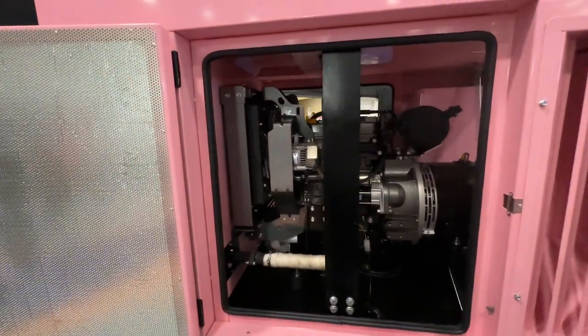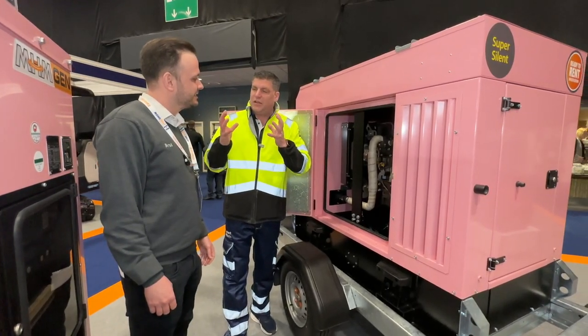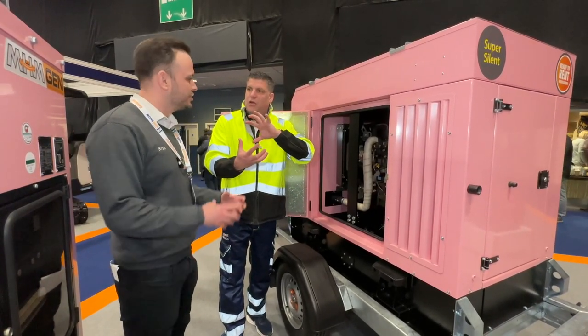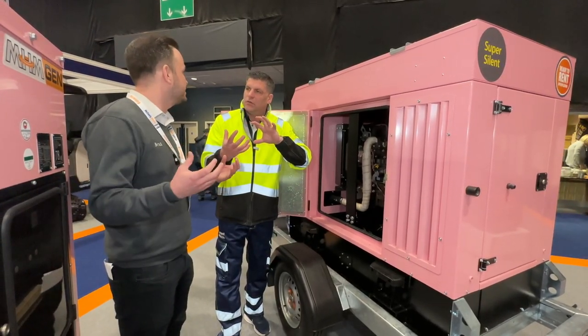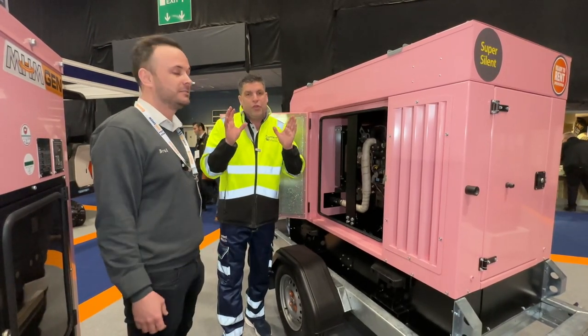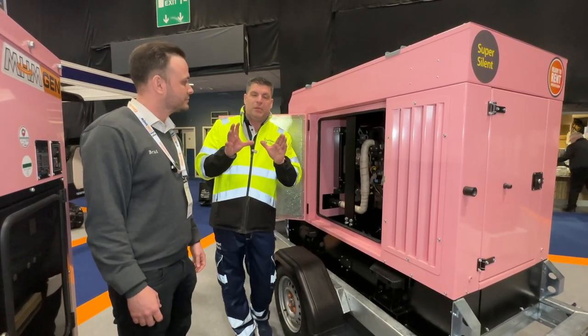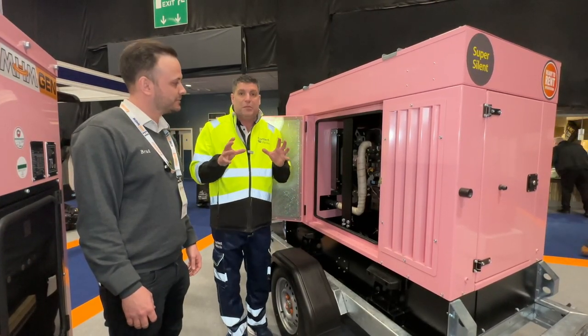It's also fully bunded, which means that if you had any sort of spillage within the generator it'll be fully contained. Inside here we've got a self-contained bund — 110% bunded — so you've got the capacity that if worst case scenario all the fuel leaked, it would be contained within the generator. That's really important from an environmental and cleanup perspective.